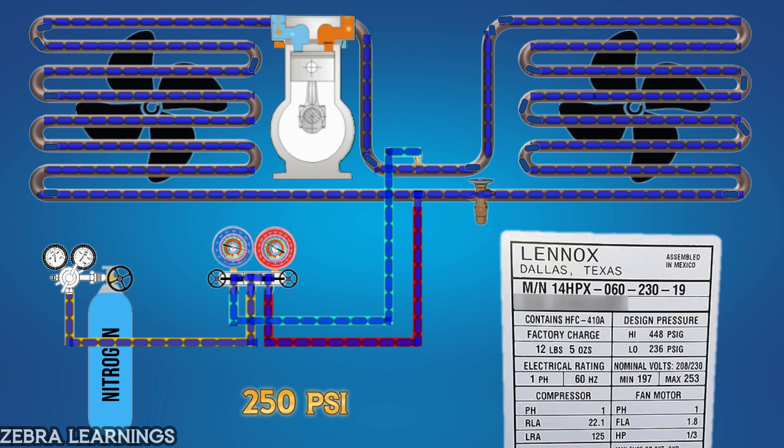Each AC unit has a maximum pressure capacity that must be observed during nitrogen leak testing. Exceeding this pressure can lead to damage to the unit's seals, gaskets, or other components, potentially causing new leaks or even equipment failure. Therefore, it's crucial to determine the appropriate pressure for nitrogen charging and adhere to that limit.